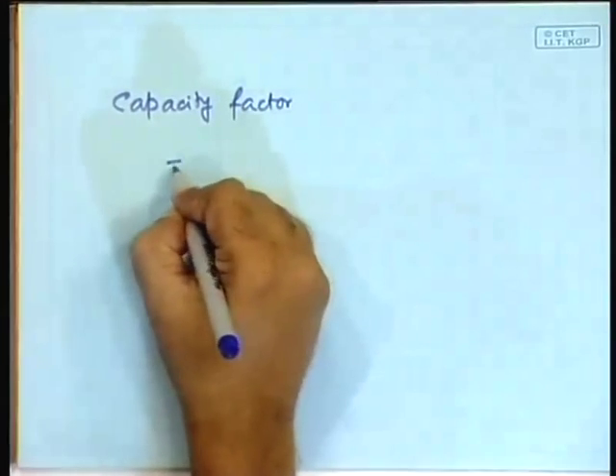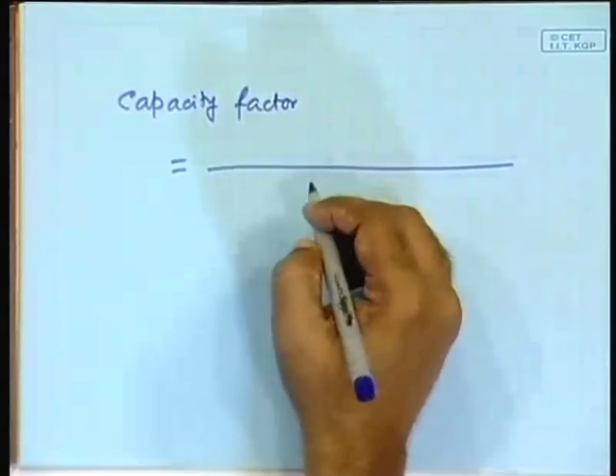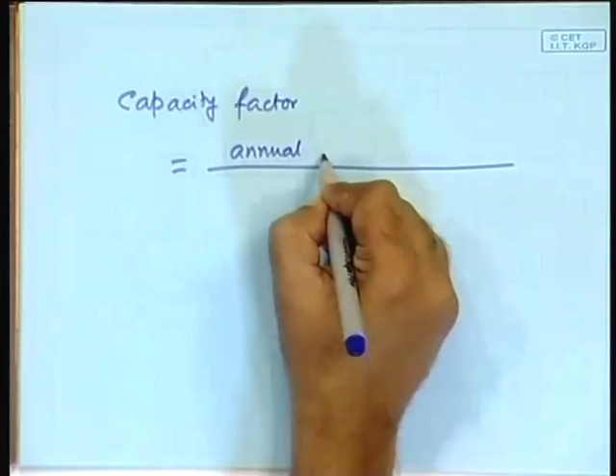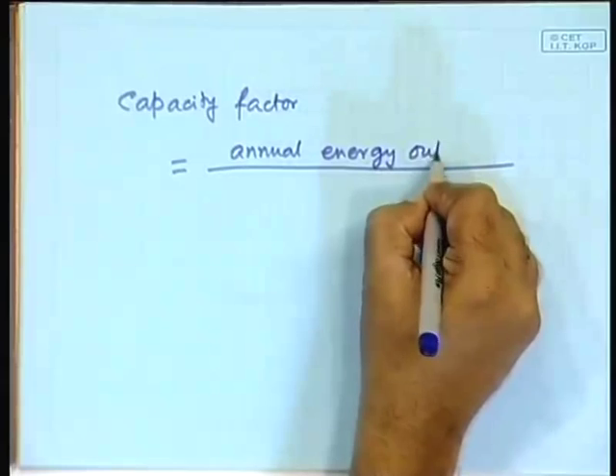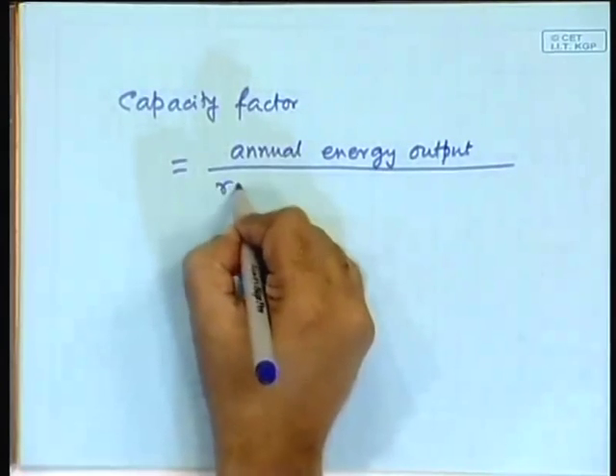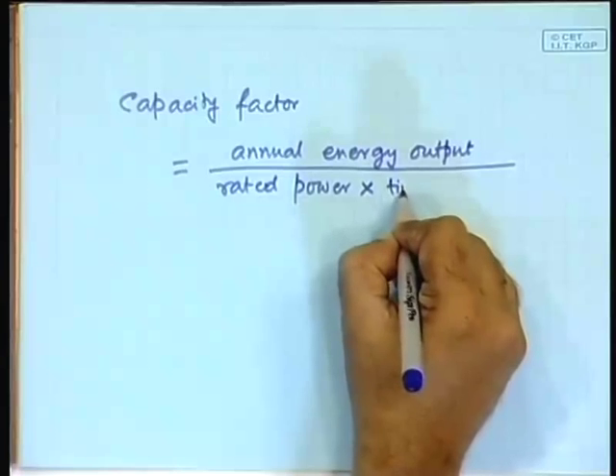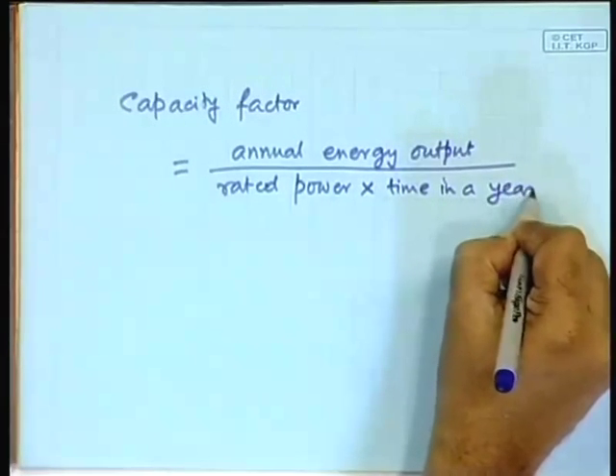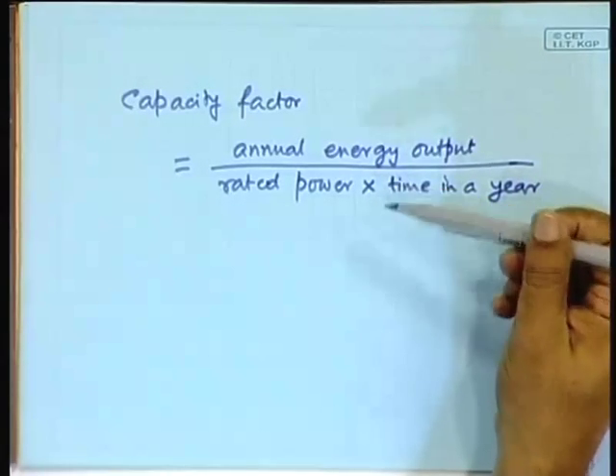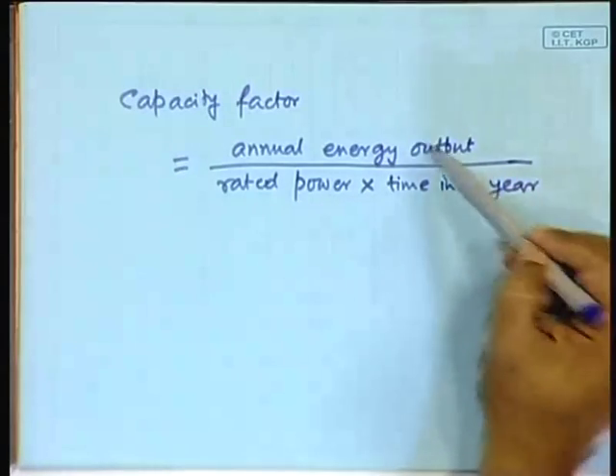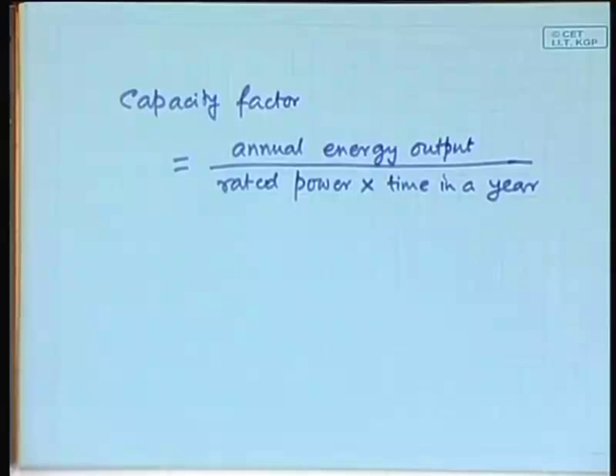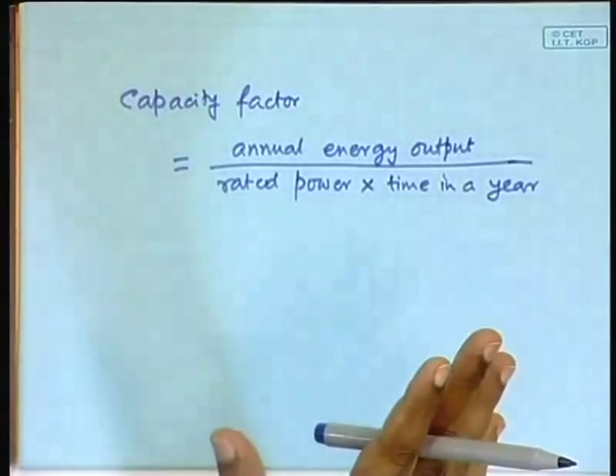The capacity factor is the ratio of the annual energy output to the rated power multiplied by time — that is, rated power times hours in a year. It is a ratio between energy and energy — power times time is energy — and this is called the capacity factor. You may have heard of the term load factor in case of conventional power plants; it is essentially the same concept: out of the whole capacity available, how much is actually utilized.